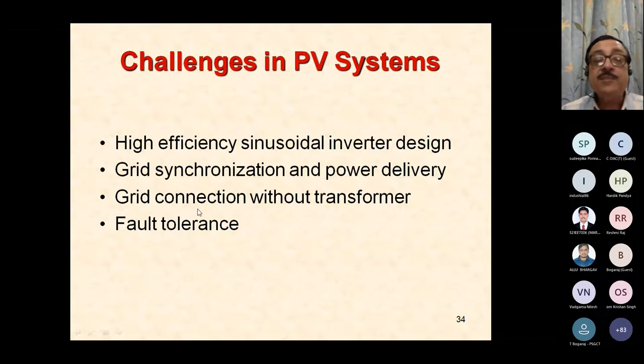It's a challenge because without a transformer, you have a lot of common mode currents and zero sequence components flowing in, and the risk of shock hazard if you touch the solar panels. So leakage currents from the solar panels are going to increase if you don't have a transformer, because the solar panels become live at the main supply voltage. So the quality of insulation of the panel is going to be put to a test.